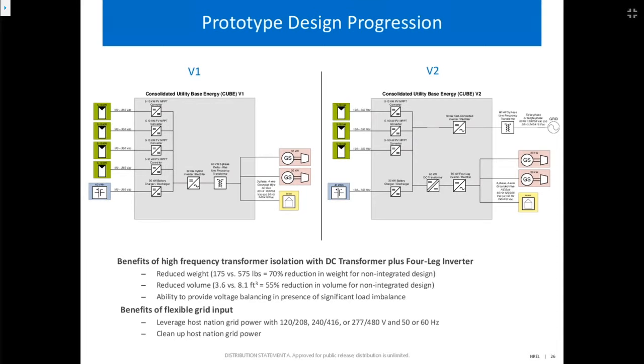Instead of the traditional 60 hertz big heavy transformer, we convert this DC to a high frequency, which allows your magnetics to get a lot smaller and lighter, but also provides the galvanic isolation needed to be able to do a 4-leg inverter and isolate the load. So this is a 4-leg inverter implementing load balancing.